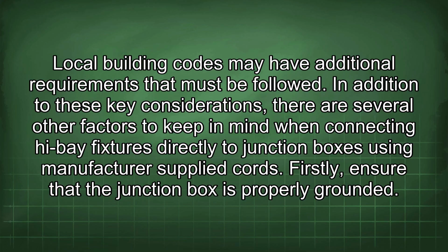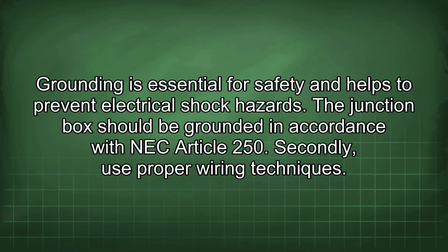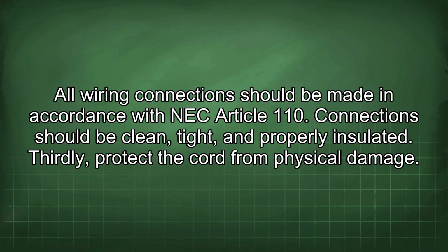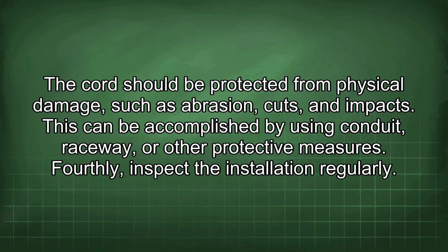Firstly, ensure that the junction box is properly grounded. Grounding is essential for safety and helps to prevent electrical shock hazards. The junction box should be grounded in accordance with NEC Article 250. Secondly, use proper wiring techniques. All wiring connections should be made in accordance with NEC Article 110. Connections should be clean, tight, and properly insulated. Thirdly, protect the cord from physical damage. The cord should be protected from physical damage such as abrasion, cuts, and impact. This can be accomplished by using conduit, raceway, or other protective measures.